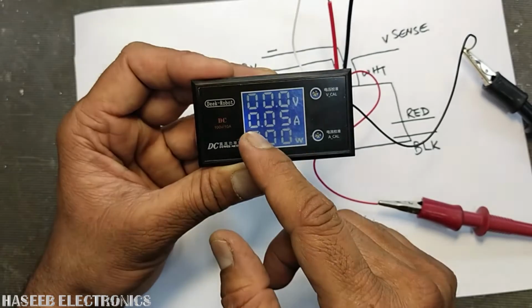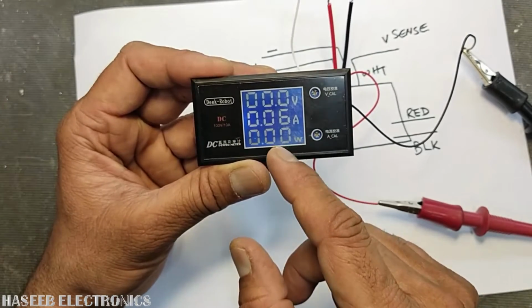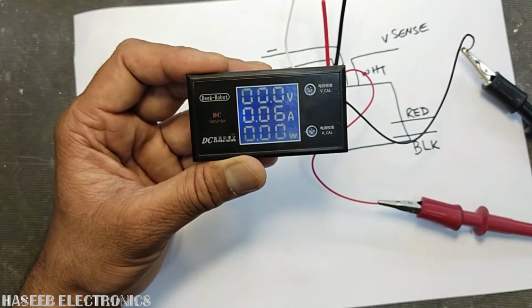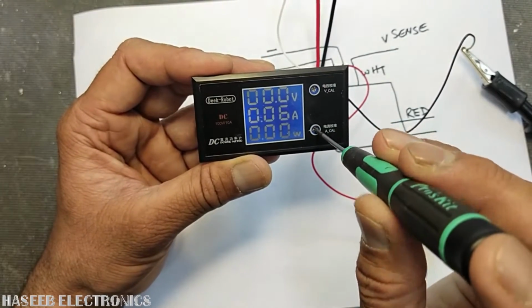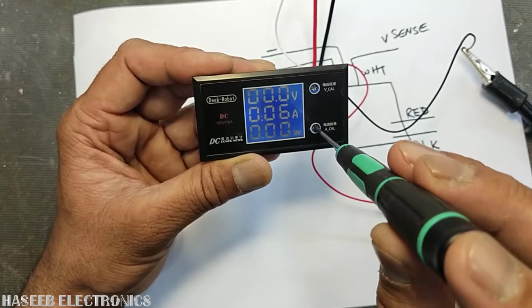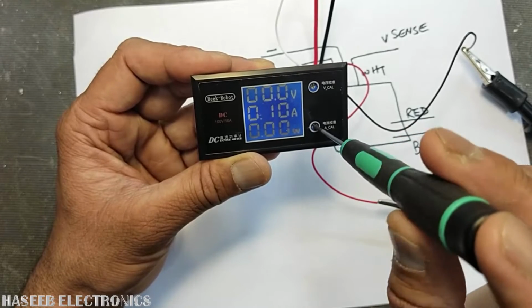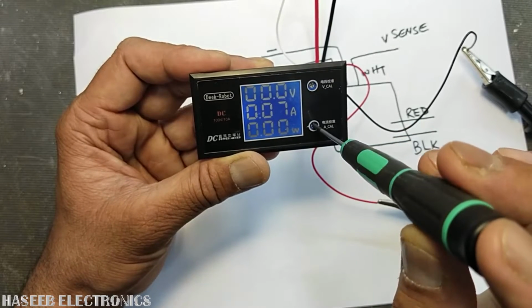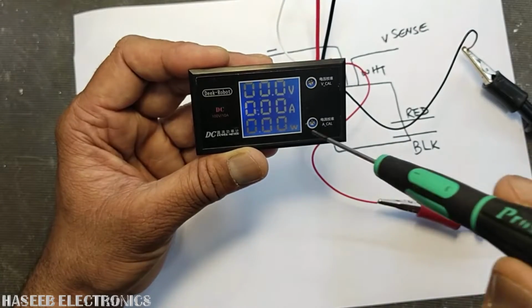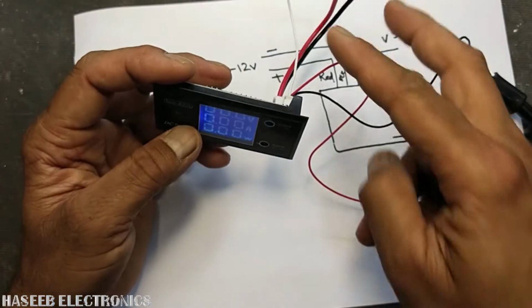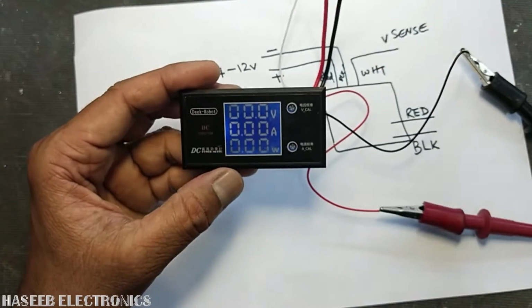It shows 0.0 volt, 0.05 ampere; this is a calibration offset. So initially we will set it to zero by adjusting this potentiometer. Now it reads zero, meaning no offset error is present.